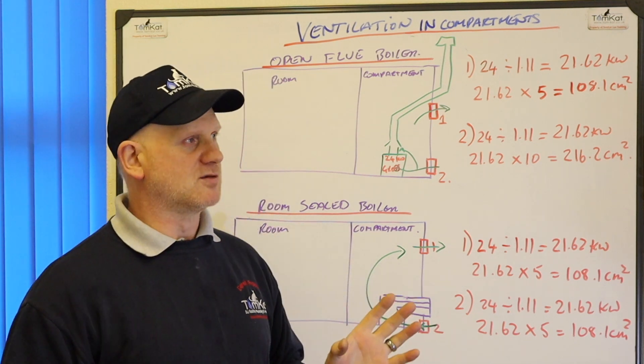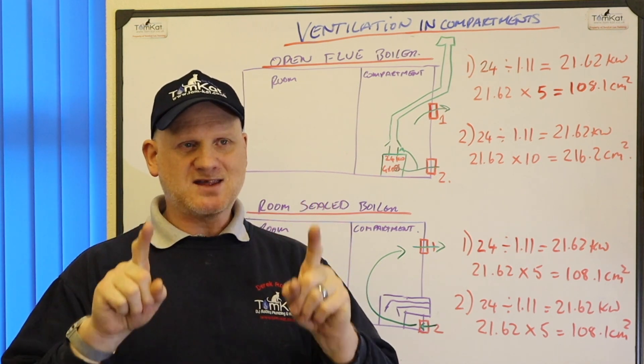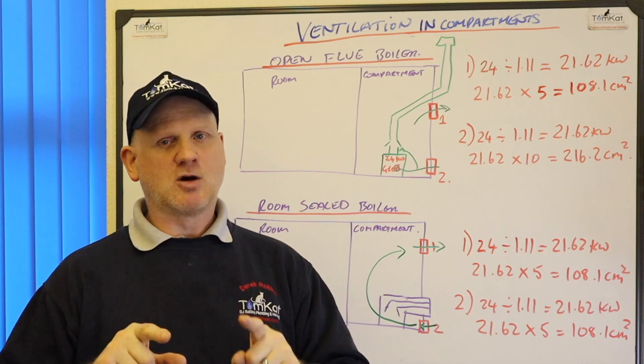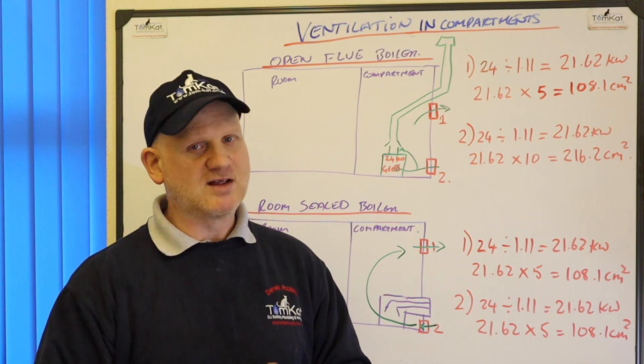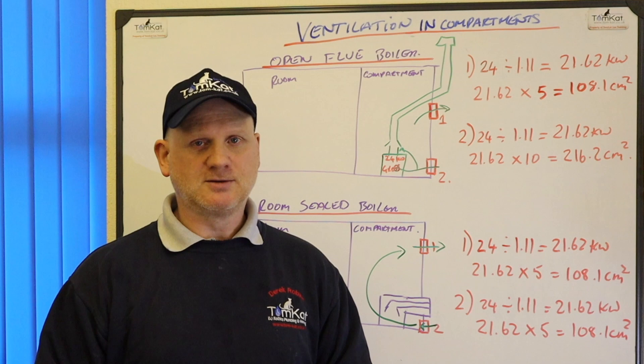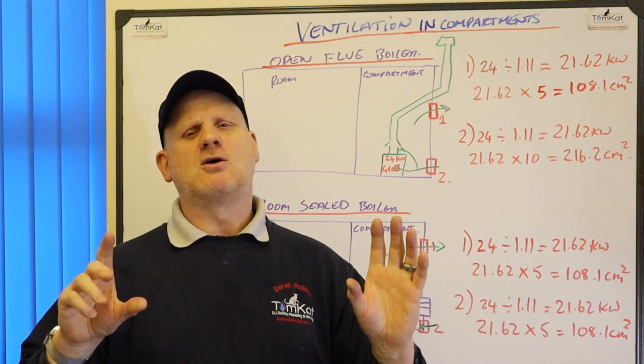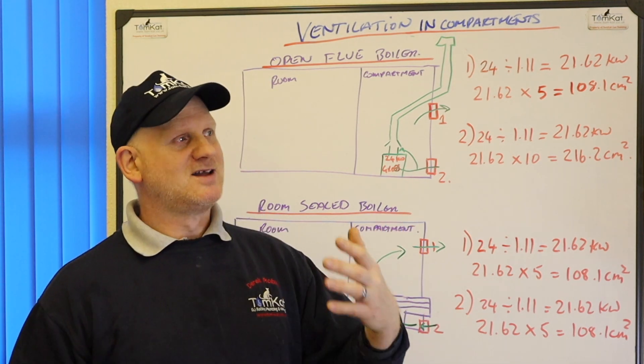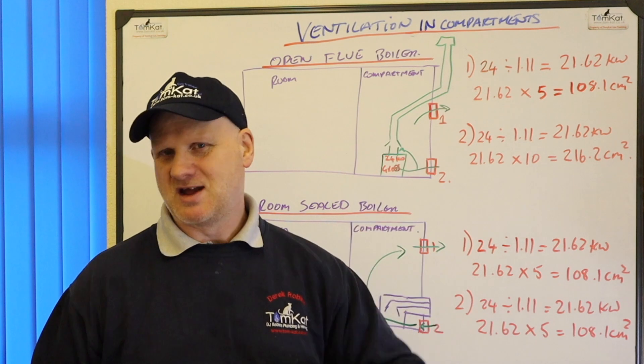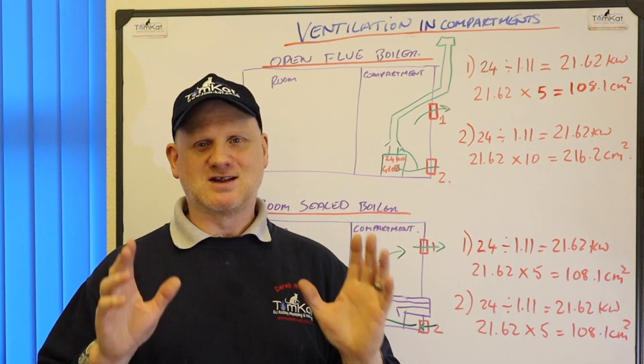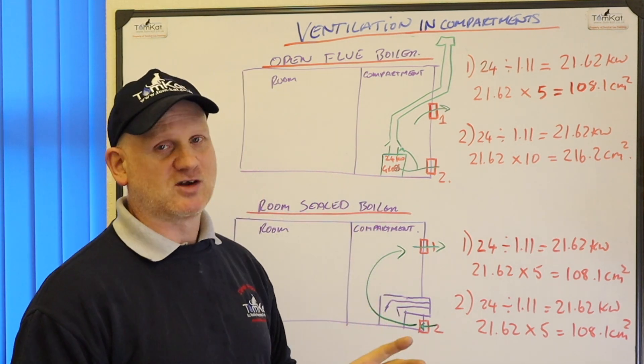Now, room sealed appliances in compartments. As I speak, as I film this video, there is no domestic boiler, condensing combi, condensing heat only, condensing system boiler that requires ventilation for combustion and ventilation for cooling. Okay. Now yes, there are a few boilers out there where you can use the air from the room. They've got specialist flues. They use old chimneys, but I'm not talking about that. I'm talking about standard installation boiler. It does not require air for combustion if it's room sealed. It gets its air for combustion from outside.